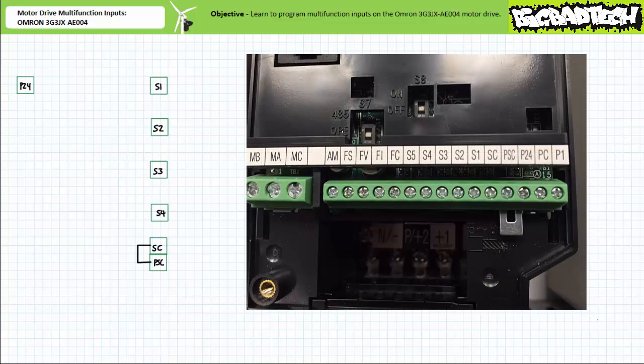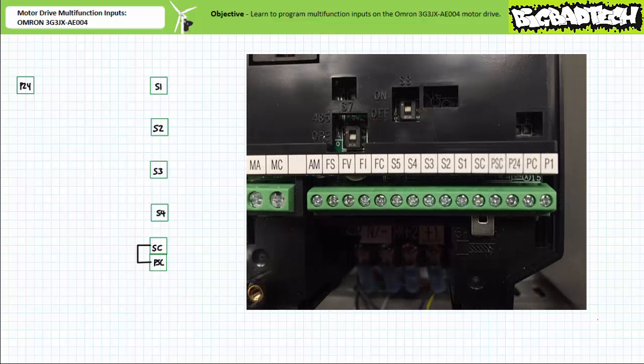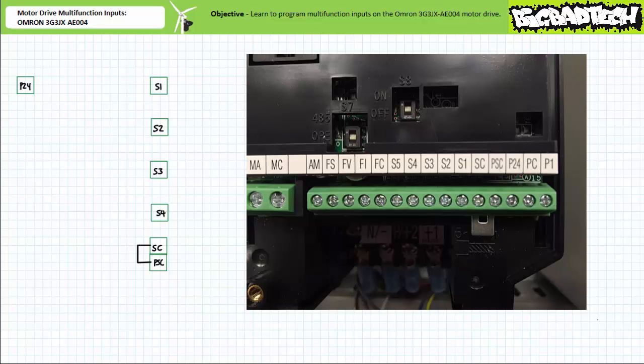The OMRON 3G3JX AE004 motor drive comes shipped with a shorting bar between terminals P24 and PSC, which assumes a sinking relationship. This is nonsense. For this reason, we'll swap the location of the shorting bar between terminals PSC and SC. This assumes a proper sourcing relationship. All is well in the universe.